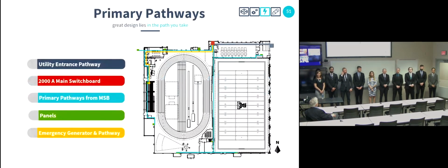Here you can see our primary pathways. We draw from the university at our utility entrance. This feeds our 2000 amp main switchboard, which feeds our various panels spaced throughout the big open area to reduce voltage drop, keeping the panels close to the loads that they serve. You can also see our emergency generator and our emergency pathway underneath the bleacher.